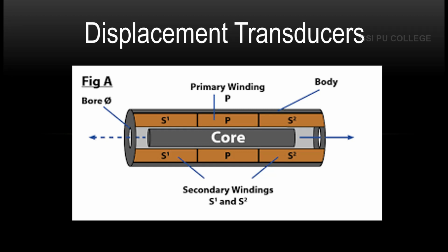It requires 3 to 4 connection wires for proper supply and output signal delivery. Physically, LVDT construction is a hollow metallic cylinder in which a shaft of smaller diameter moves freely back and forth along the cylinder's long axis. So here you are going to find a core, which is called a shaft, which can easily move back and forth.